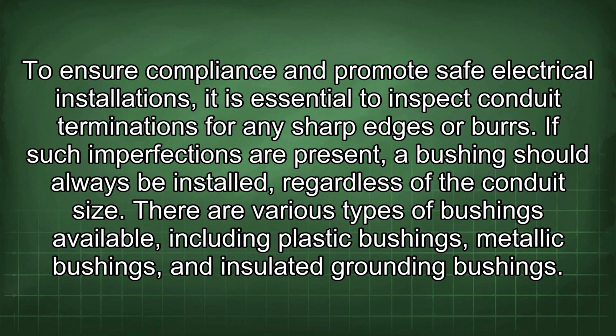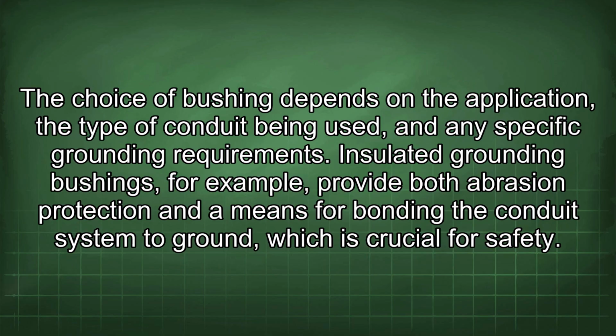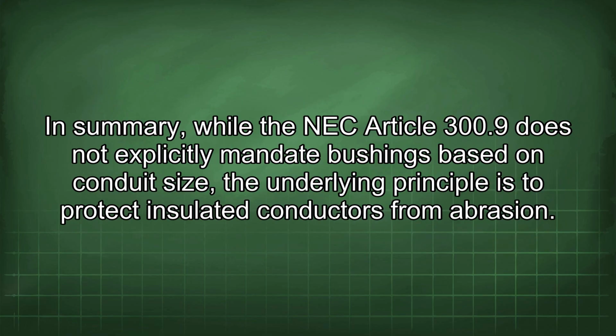There are various types of bushings available, including plastic bushings, metallic bushings, and insulated grounding bushings. The choice of bushing depends on the application, the type of conduit being used, and any specific grounding requirements. Insulated grounding bushings, for example, provide both abrasion protection and a means for bonding the conduit system to ground, which is crucial for safety.